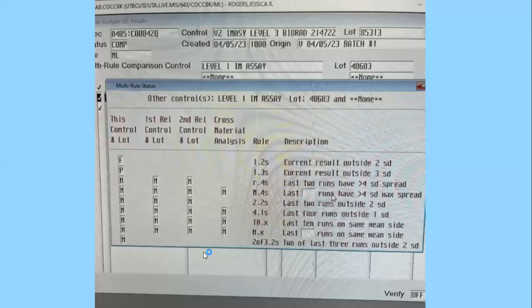If it does not run correctly, this is the box that will pop up if you try to approve the results. It is just saying that it is out of range, so you just click enter. A similar box will pop up and all you will type in is what you did. So we will type in rerun and rerun the QC on the analyzer. If that doesn't work, we'll bump the flex pack off and put on a new one or put on the old one. And we'll just put in bump pack if we do that.